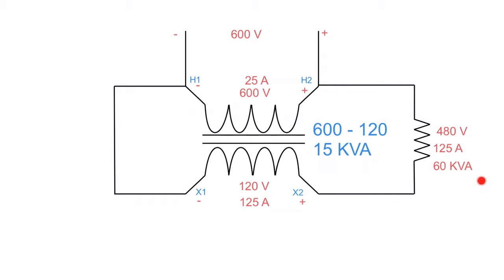We've got a 60 kVA load. The next step is to determine the line current. Knowing that power in equals power out, if the load is asking for 60 kVA, the source must supply 60 kVA. With a line voltage of 600 volts, 60,000 divided by 600 volts gives a line current of 100 amps.